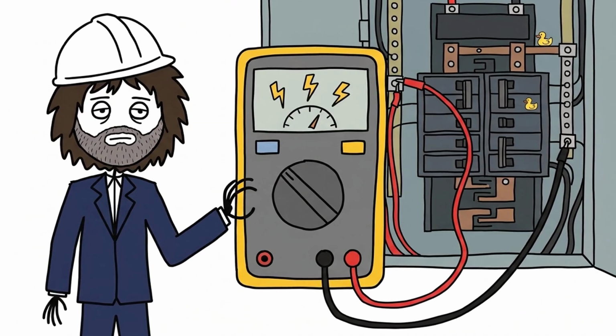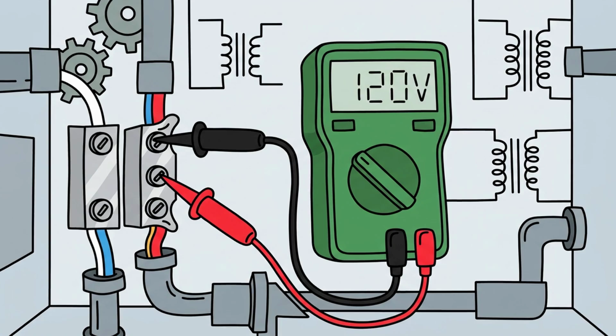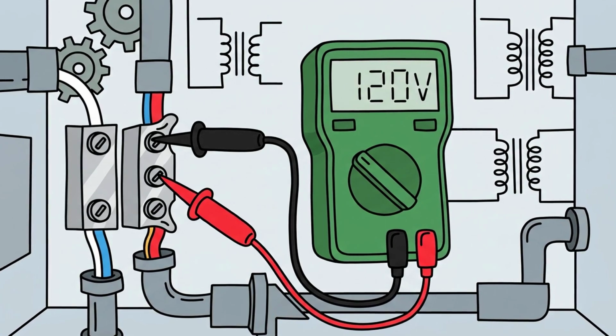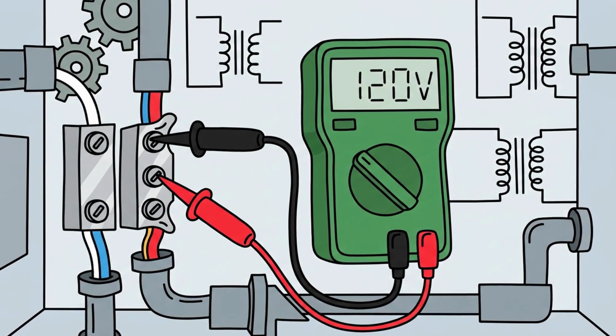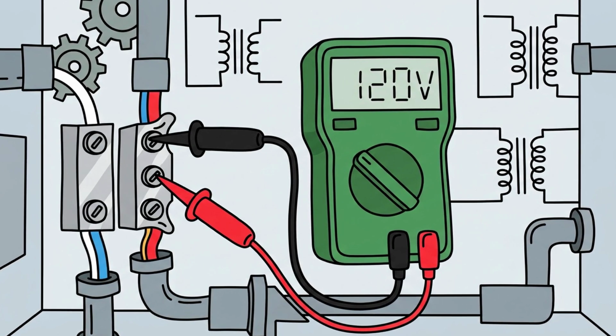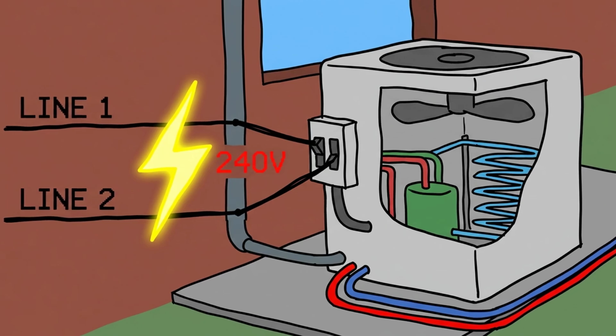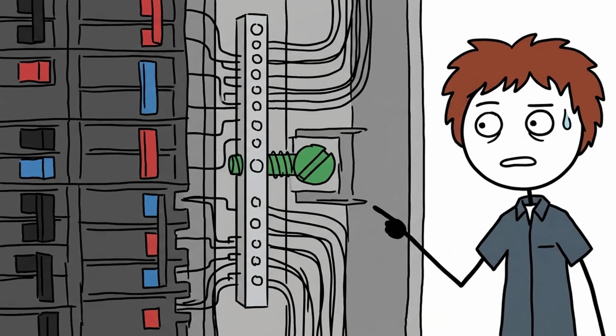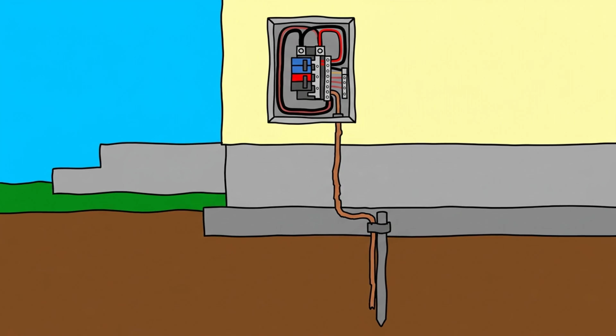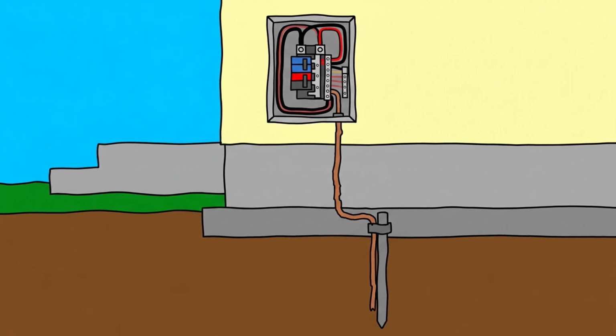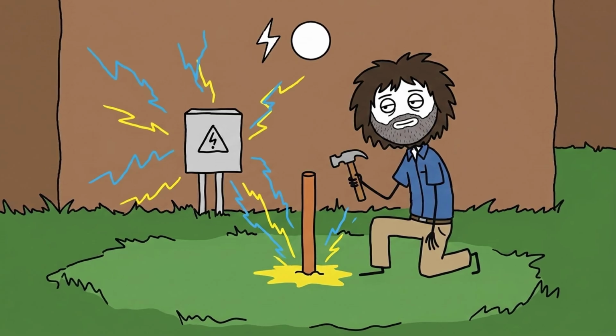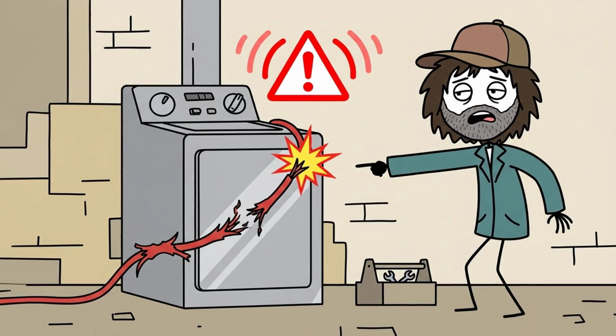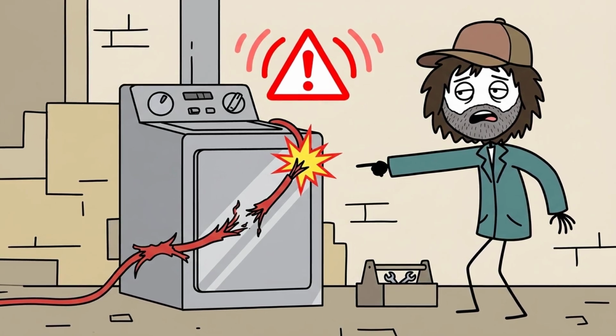Inside every standard circuit breaker sitting in your panel box, two separate mechanical triggers stand ready to interrupt electrical flow: a thermal trip mechanism for slow overloads and a magnetic trip mechanism for instantaneous short circuits. The thermal trip mechanism handles gradual overloads. Imagine plugging a space heater, hair dryer, and vacuum into the same 15-amp circuit. Total current draw rises to 22 amps. A 15-amp breaker will not trip open instantly under this load.